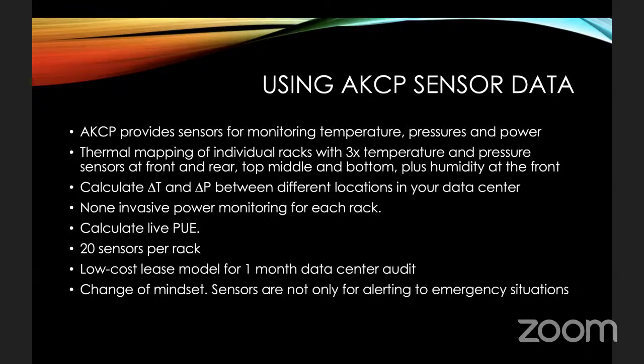So with the AKCP setup, you will have 20 sensors per rack. That sounds like a huge amount, right? So let's run through them. We've got 3 temperature sensors at the front, 3 temperature sensors at the rear, top, middle, and bottom. That's 6 sensors. We then have the delta T, front to rear, top, middle, and bottom. That's another 3. So you're up to 9 sensors. We then have differential pressure, top, middle, and bottom. So that is 12 sensors. We then have the pressures at the front and pressures at the rear, which is another 6, which are up to 18 sensors. And then we have voltage and current, which is 20 sensors per rack.